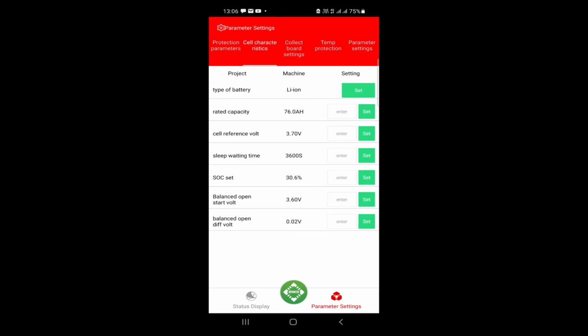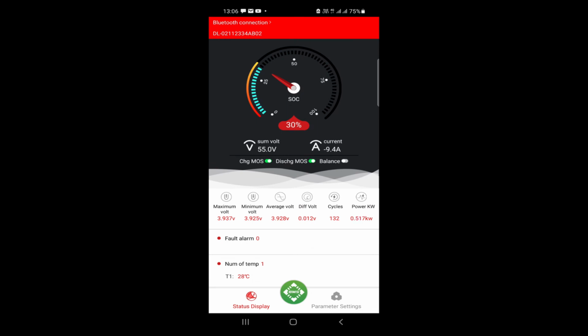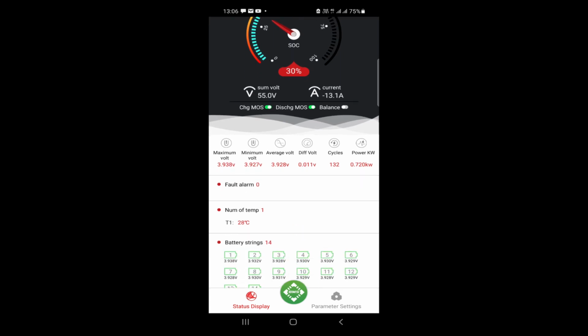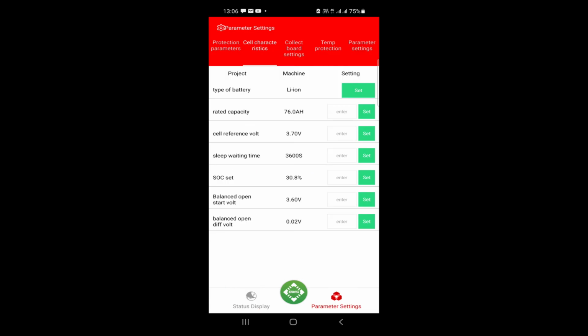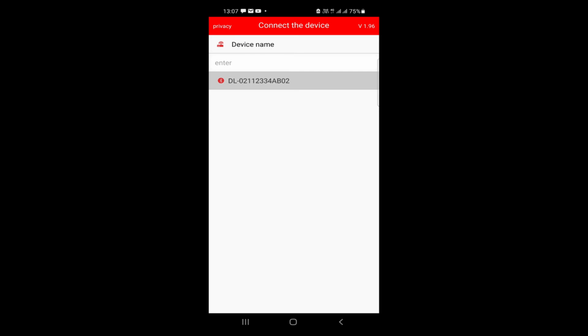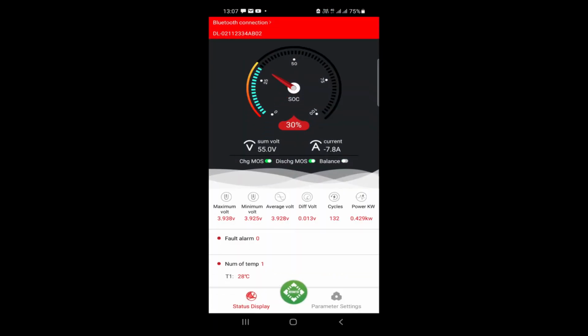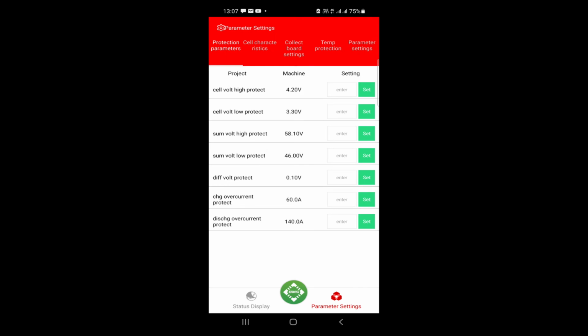Now, how to set the SOC. What I recommend for a 14S Leaf module is that you set the lower voltage as 50 volts and the highest as 57.4 volt. That is what my settings are. You can adjust any other way. So once the voltage is at 50 volt, you have to go to the parameters and set it as 0 here. Once the battery is fully charged, or when it is at 57.4 volt, again you go to the parameters SOC and set it to 100%. Then your SOC will be correctly displayed on your charge indicator as well.